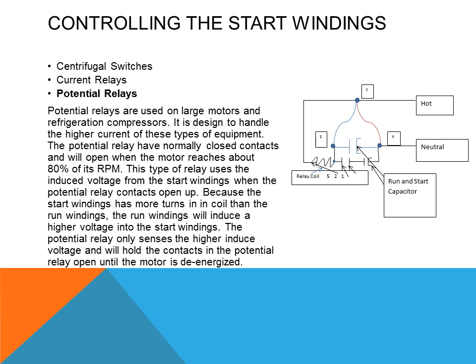Potential relays are used for larger motors and compressors and are designed to handle higher current. Potential relays are sometimes called voltage relays because they use the inductive voltage from the start windings to generate a voltage higher than the applied voltage. This inductance sends voltage to the relay coil, which only senses the higher inductive voltage. The potential relay has a normally closed set of contacts that will open once the inductance increases in the start winding, and will remain open until the compressor is de-energized.